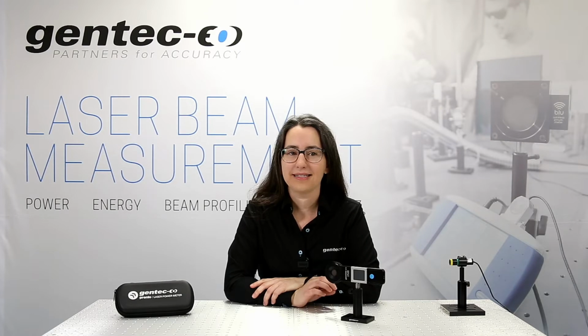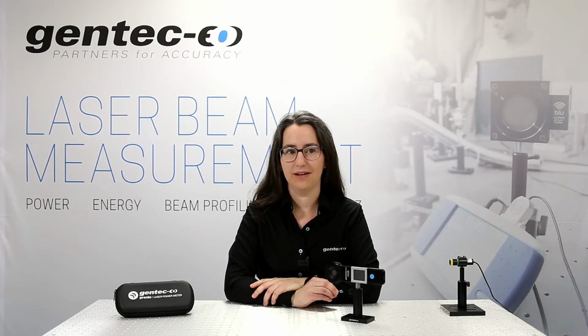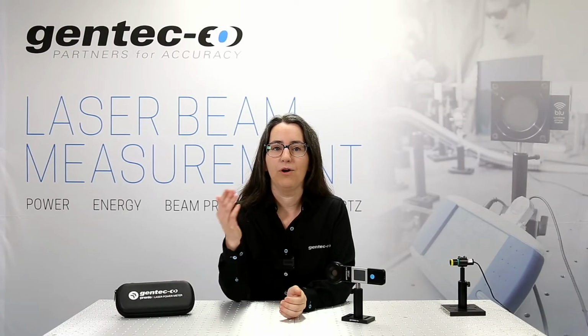Each sensor reacts slightly differently to light at different wavelengths. And from one sensor to another, even though they're built the same way, there are minute differences in the sensitivity curve. Because we want to give you the most accurate measurements possible, we calibrate each unit that we build. During the calibration process, we determine your sensor's sensitivity with high precision for every wavelength from 193 nanometers to 2,100 nanometers. We print out the calibration factors on a calibration certificate that's included with your product, and they're also logged in the PRONTO's internal memory.